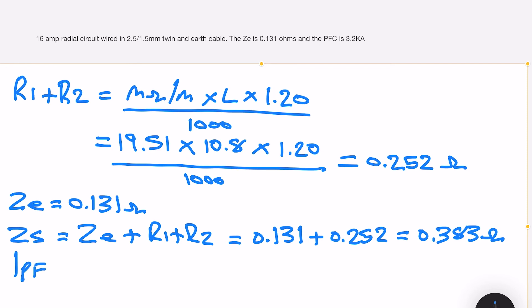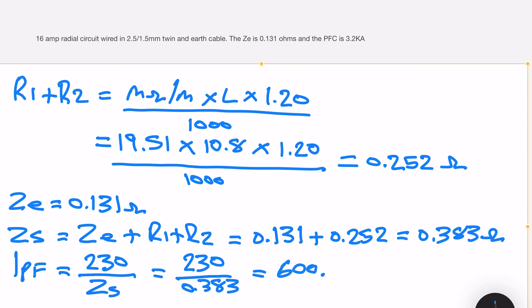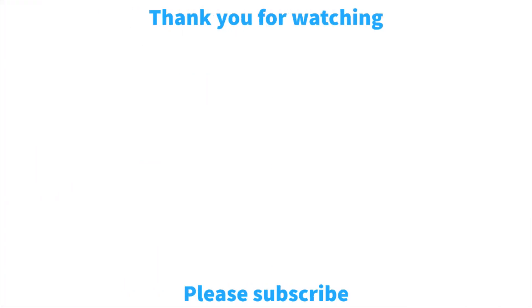To find the fault current IPF, we divide the voltage by ZS. So that's 230 volts divided by 0.383, which gives us an answer of 600.522 amps. You'll notice the difference between the short circuit current and the fault current — as mentioned before, the short circuit current is usually much higher. Thank you for watching; I hope you found this video useful — if so, please subscribe to see more videos like this.